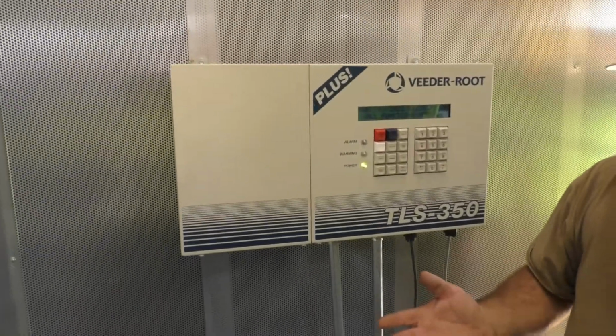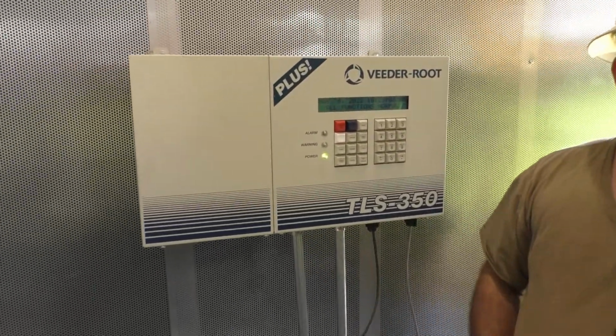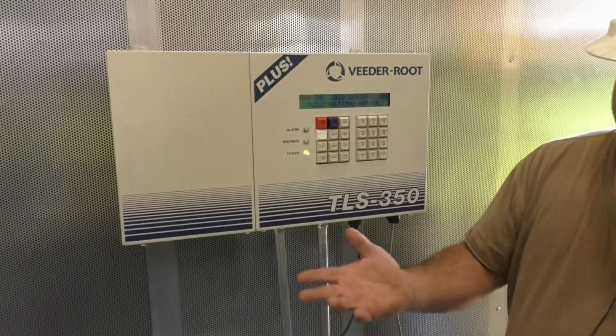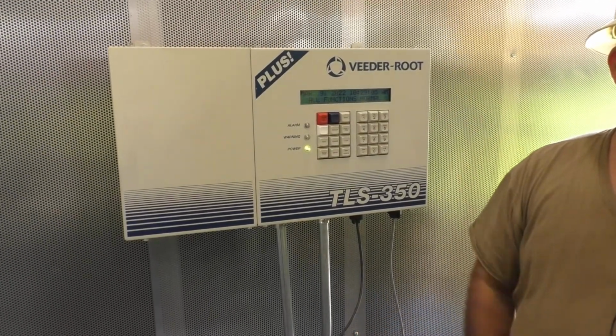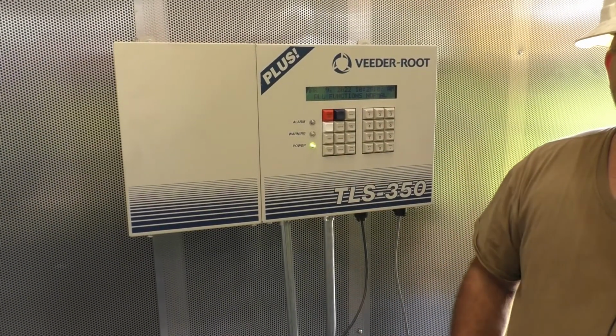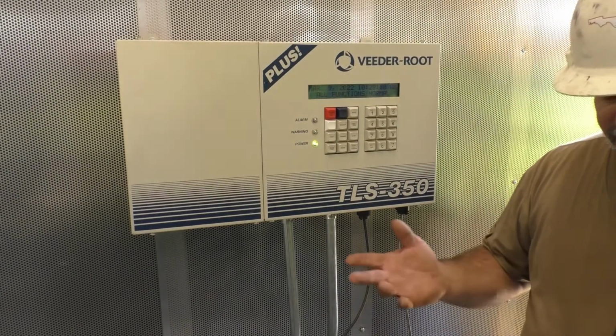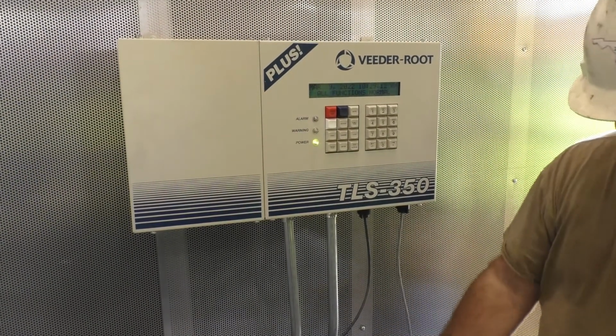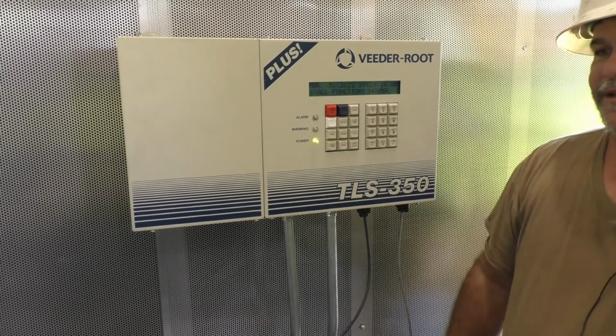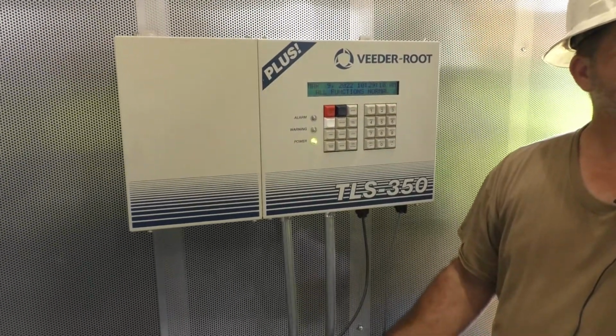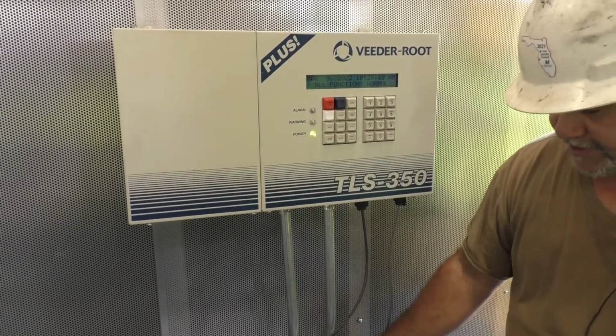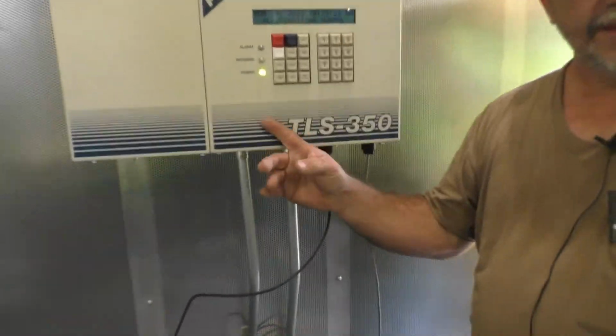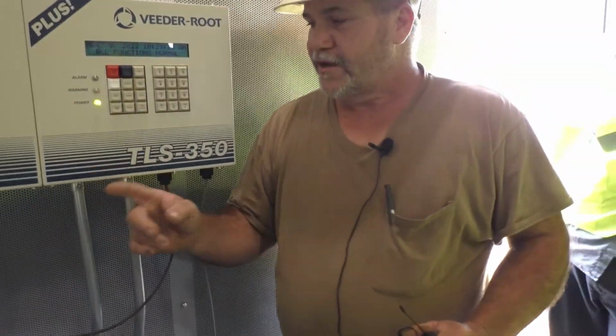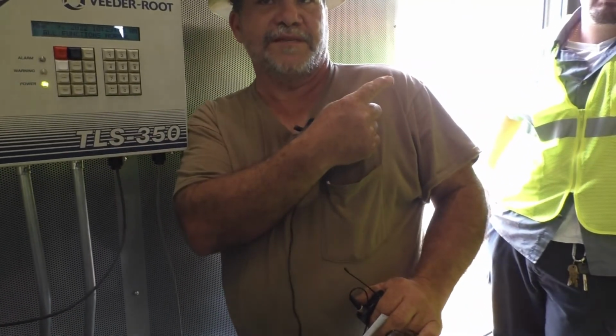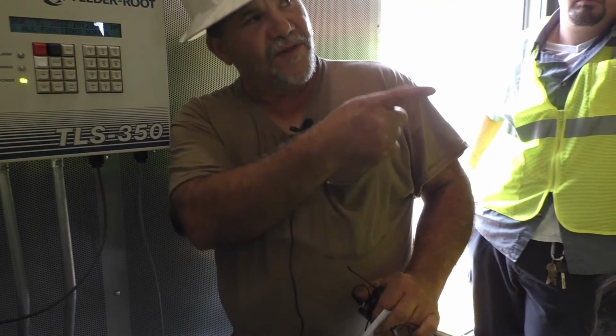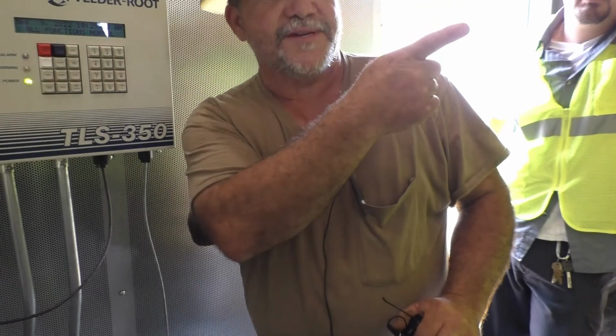So anyhow, other than that, there's no printer on it, so I can't show you how to load paper. But that's about it. I mean, the alarms are pretty descriptive. You're only going to have a couple: overfill, low product, max volume. If he gets to the interstitial, yeah, interstitial. The interstitial sensor will not only alarm on this console, it will also set the external alarm off.